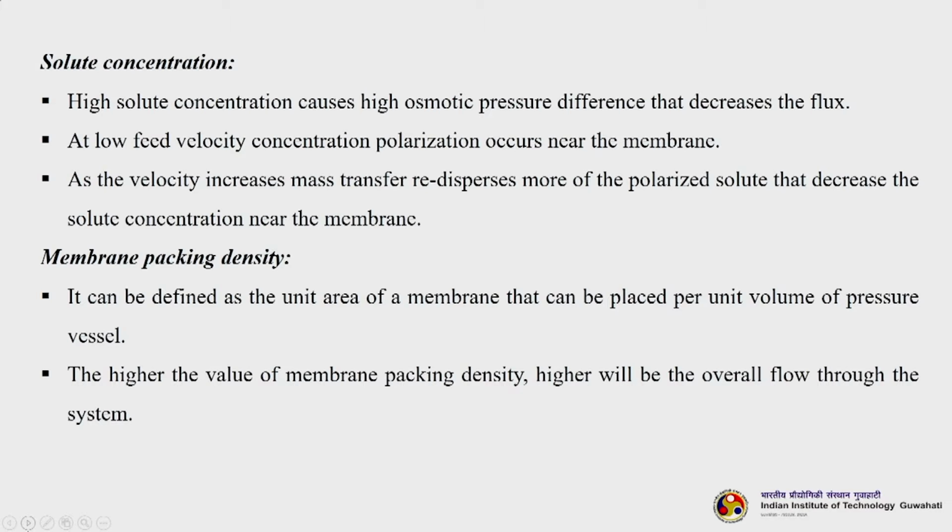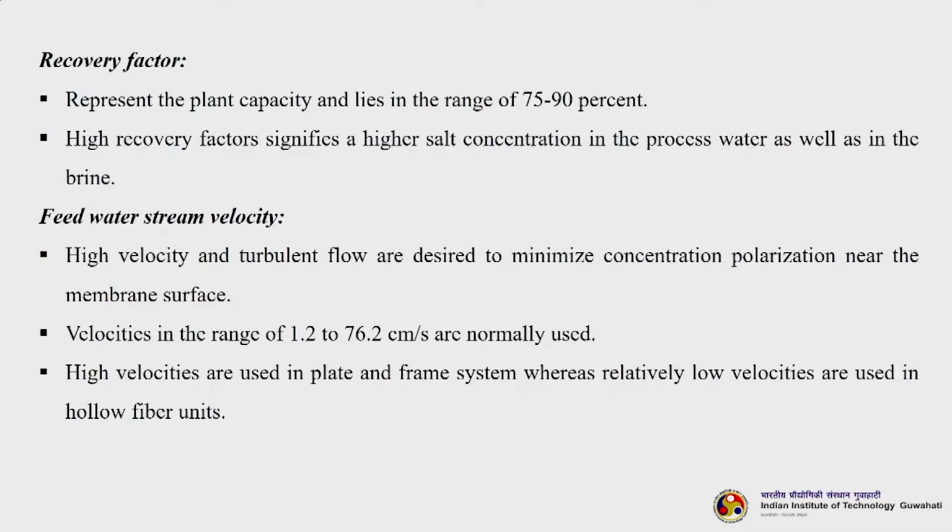The next parameter is membrane packing density. This is one of the most important parameters. You can define membrane packing density as the unit area of a membrane that can be placed per unit volume of pressure vessel. The higher the value of membrane packing density, the higher will be the overall flow through the system. The next one is recovery factor. It represents the plant capacity and lies in the range of 75 to 90% usually. A high recovery factor signifies a higher salt concentration in the process water as well as in the brine.